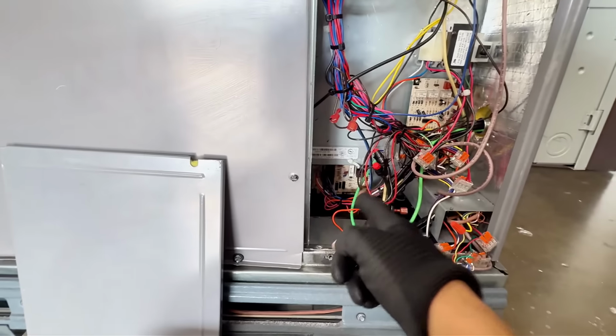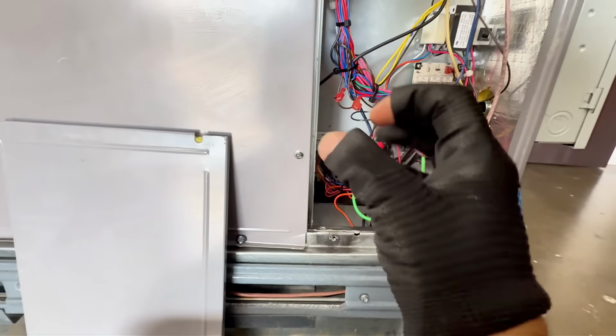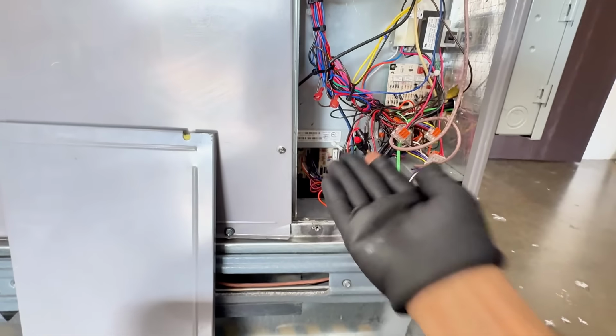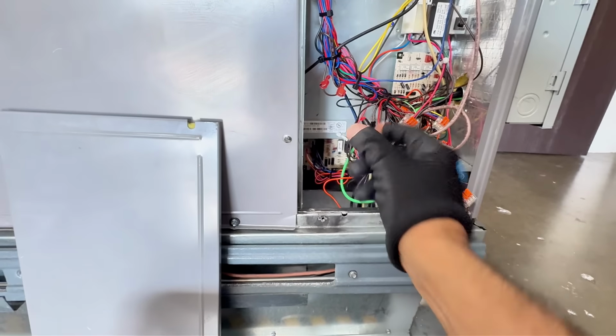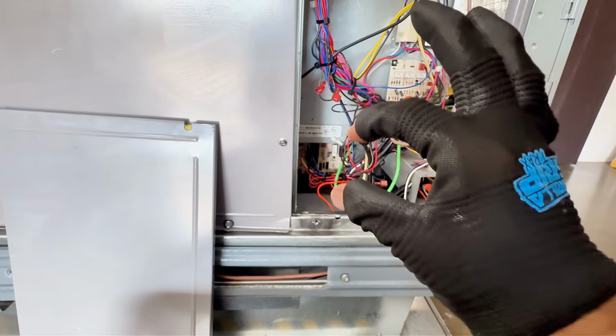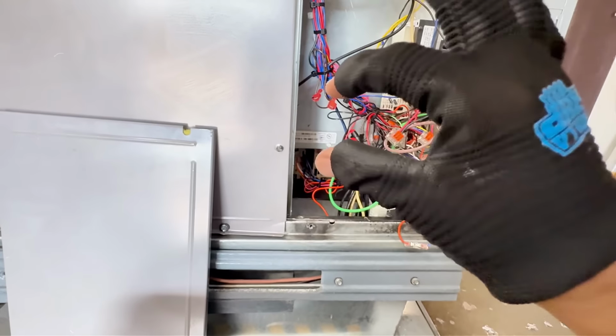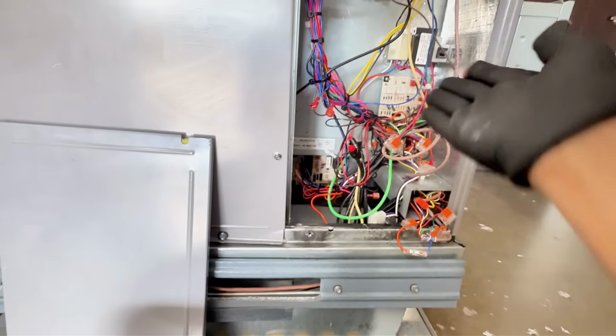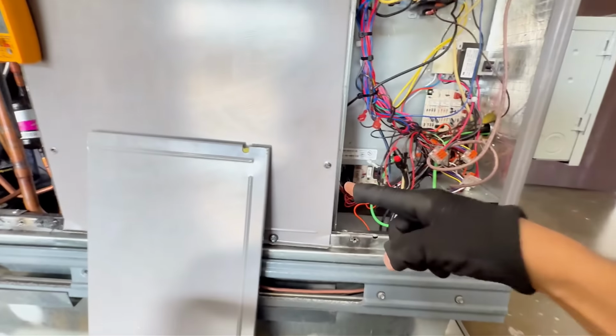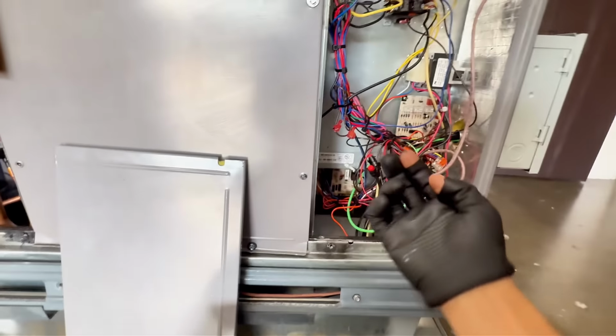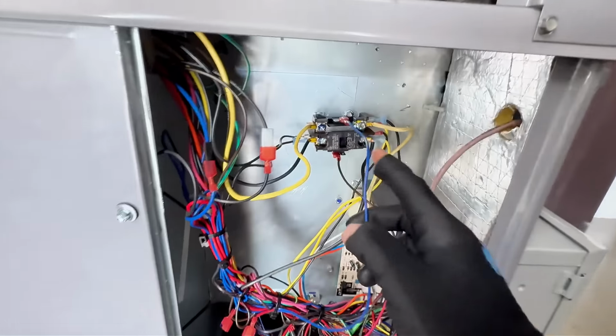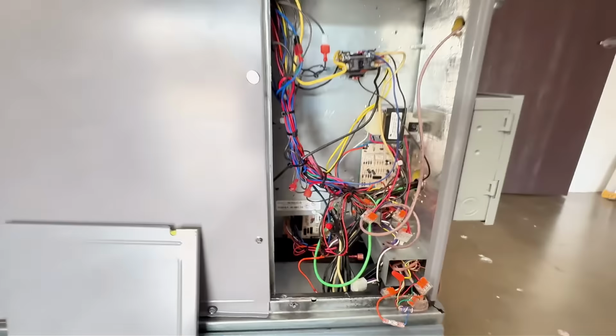And then from that little Molex connector that I showed you, that was the service call that we fixed. It was put on incorrectly. Instead of it being here, it was put incorrectly, and one pin was missing. So all I had to do was put it back. Once it sends 24 volts back, it sends it this way, which is my blue wire, goes to my contactor coil, and that was it. That was the service call.